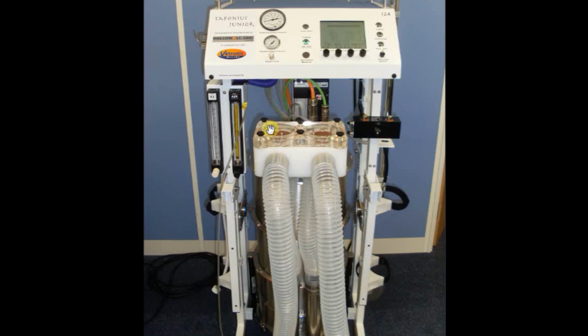At the front here we have the main valve block, which has a clear perspex lid showing clearly the two valves from the inspiratory, which is on the left side, and the expiratory side, which is on the right side. This clear lid is held in place by 6 black thumb screws, and these can be removed to take the lid off, remove the valves, and do a thorough clean. Here we have the two 2-inch patient tubes which will lead down to the Y piece, which we'll see later, and to the back here we can see just a bit more of the cylinder.